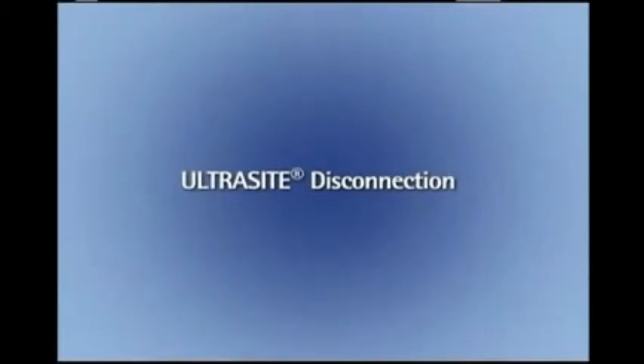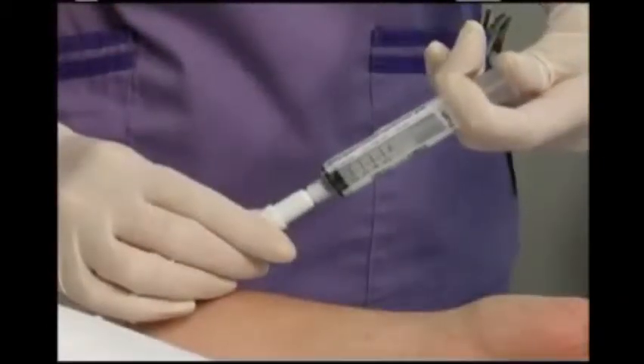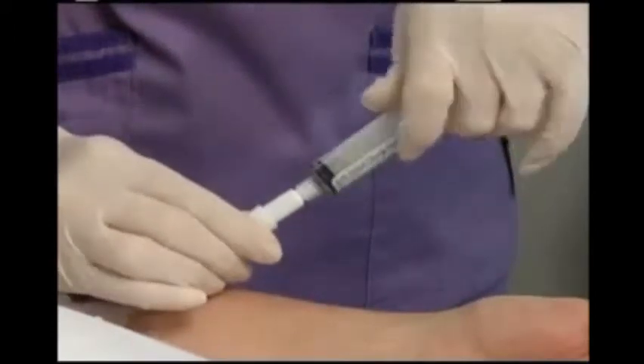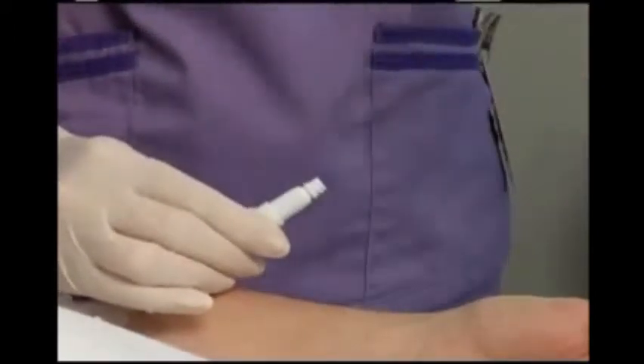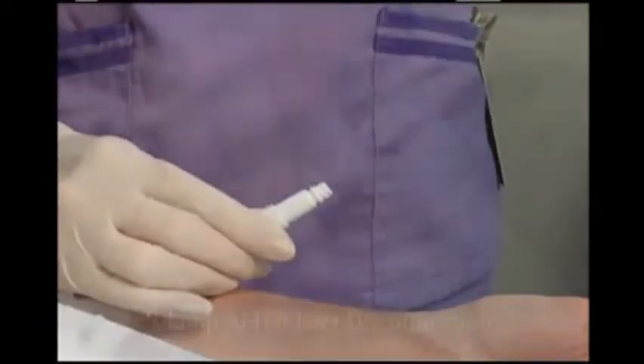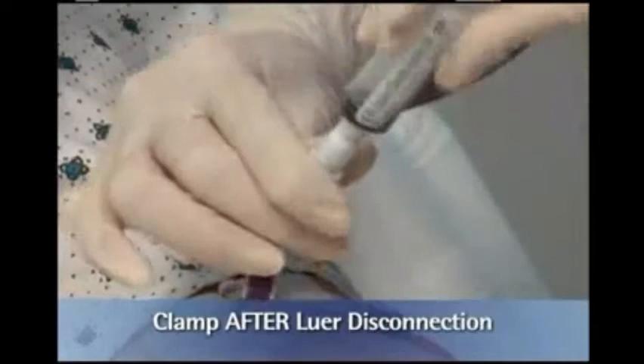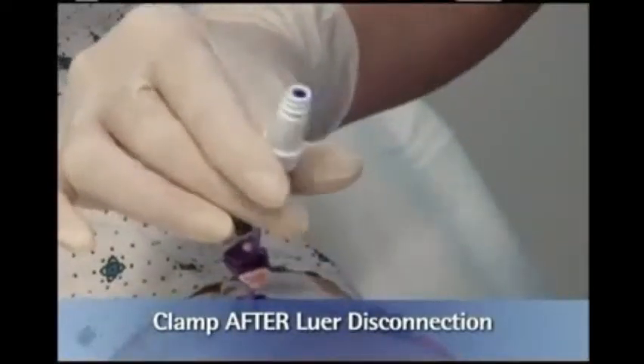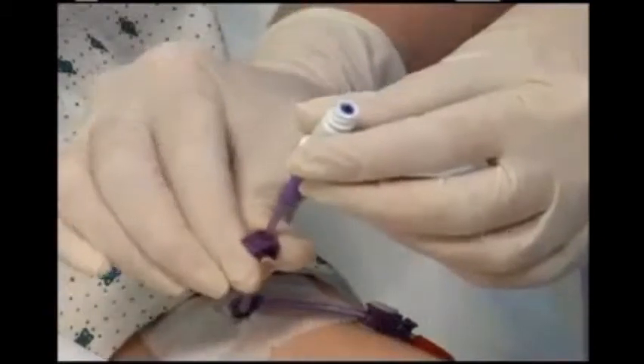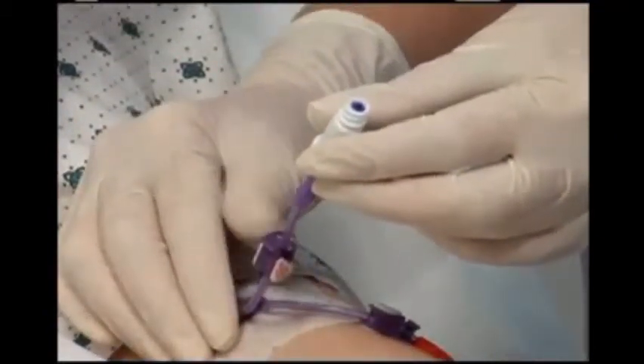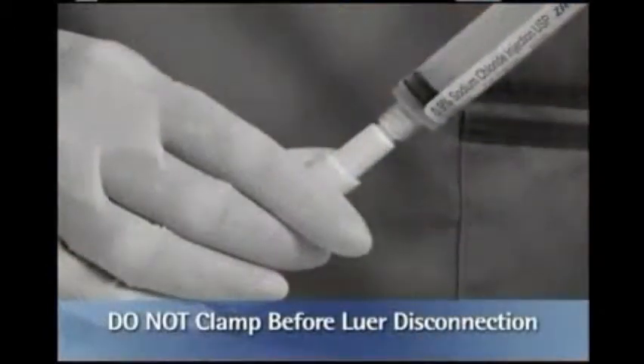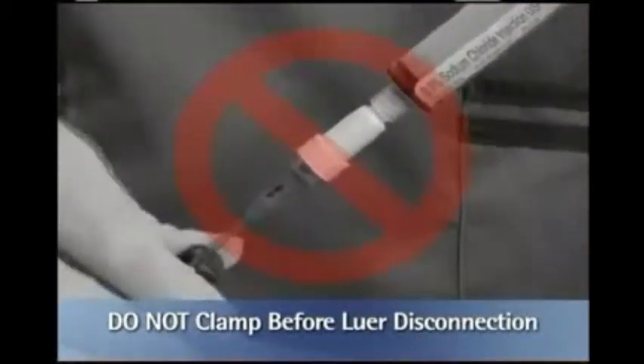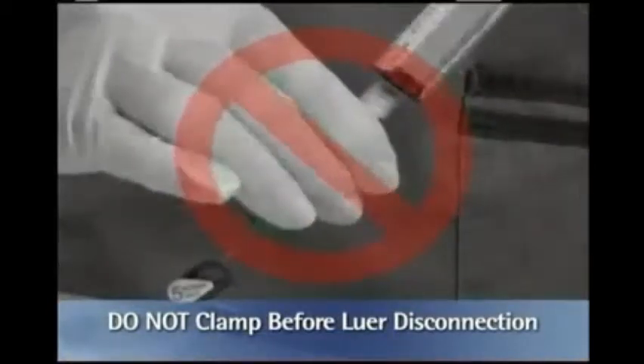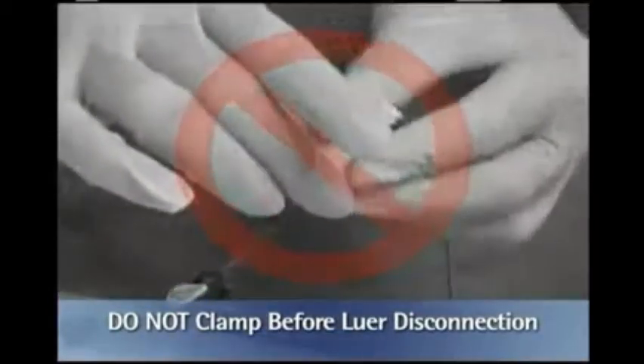The clinician has finished administering the final flush solution and is now ready to disconnect the syringe. Clamping the IV line is not necessary with the Ultrasite Luer access device. However, individual healthcare facility protocols may require IV lines to be clamped when not in use. If the IV line is to be clamped, it should be clamped after disconnecting the syringe to allow the positive displacement to occur. This will help decrease the incidence of catheter occlusions. It is important to remember that you should not clamp the line before disconnecting the syringe because it will prevent the positive displacement action from occurring.